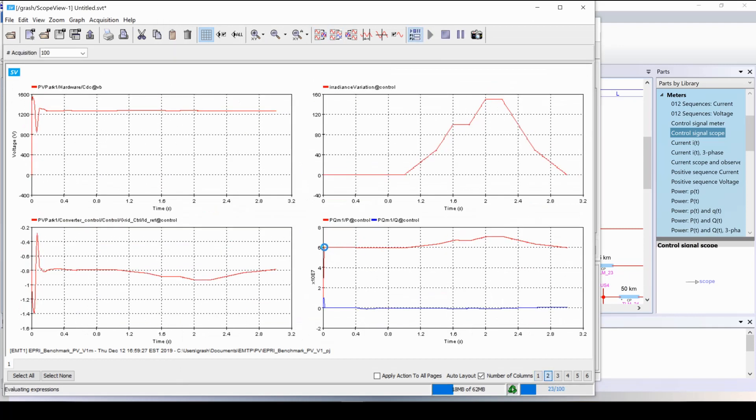As we can see, initially the park produced the same active power as during load flow, 60 megawatts. We can also see that the initialization is perfectly done. At this point, one second, the irradiance is varied. And we can see the active power of the park is varied as well.